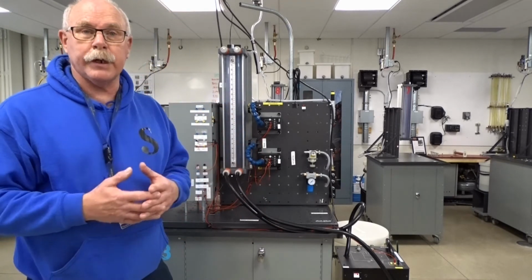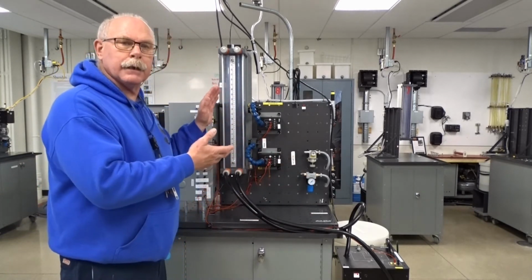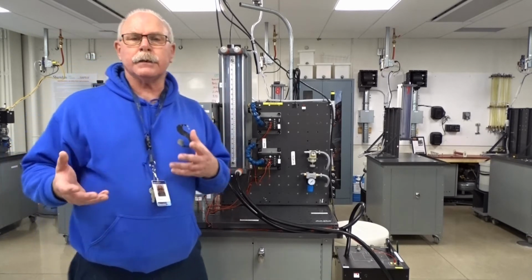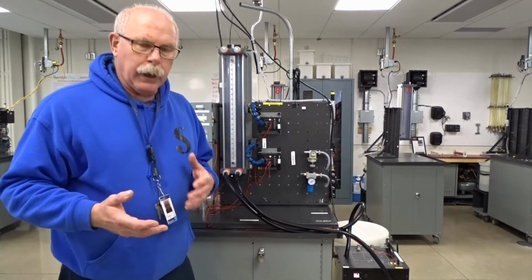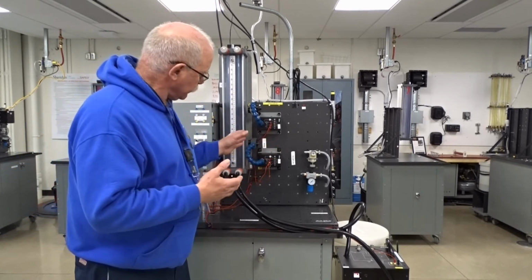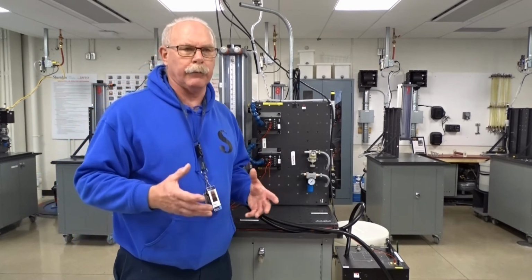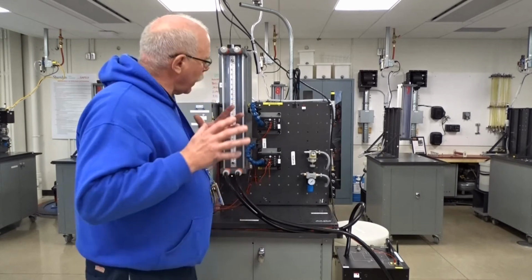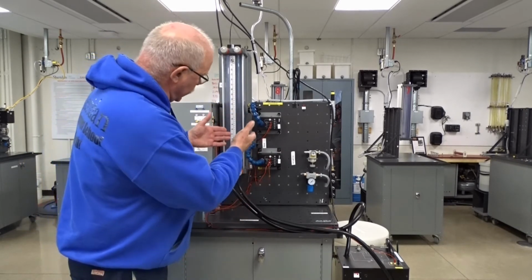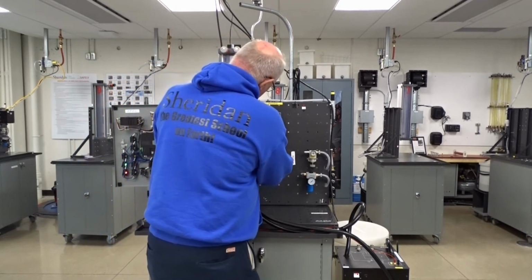Now the dead time can change depending on the load on the system, but the dead band is something that has been adjusted in this system. In this type of control, since we have water being detected by these capacitance detectors, the only way we can change the liquid level, or in fact the set point, is by moving these detectors. What I'm going to do is shift one up a little bit. So what I'm changing here is the dead band. Move this up.